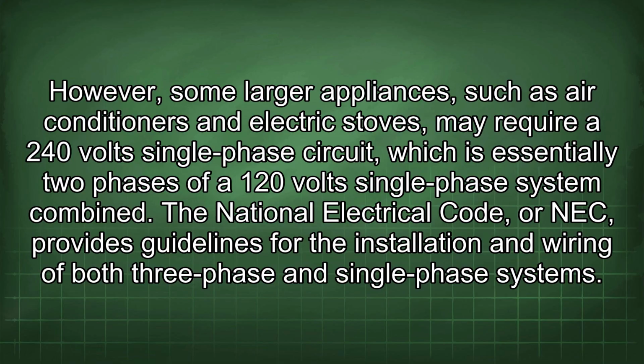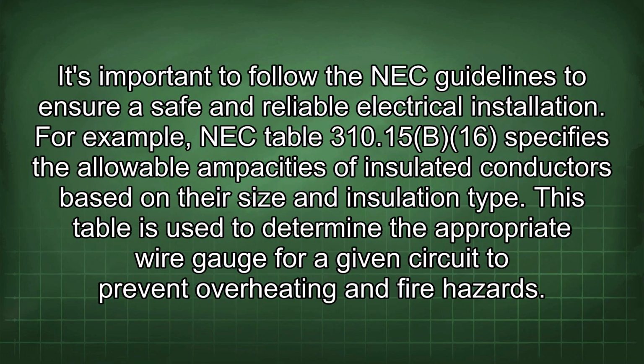The National Electrical Code, or NEC, provides guidelines for the installation and wiring of both three-phase and single-phase systems. It's important to follow the NEC guidelines to ensure a safe and reliable electrical installation. For example, NEC Table 310.15(B)(16) specifies the allowable ampacities of insulated conductors based on their size and insulation type. This table is used to determine the appropriate wire gauge for a given circuit to prevent overheating and fire hazards.